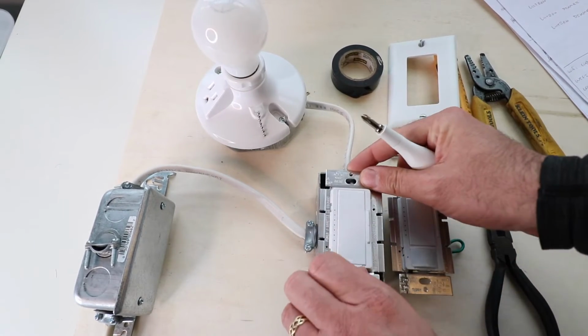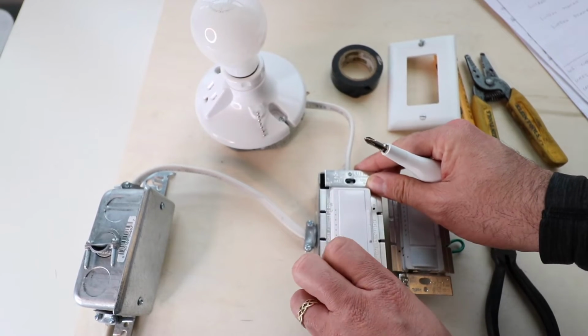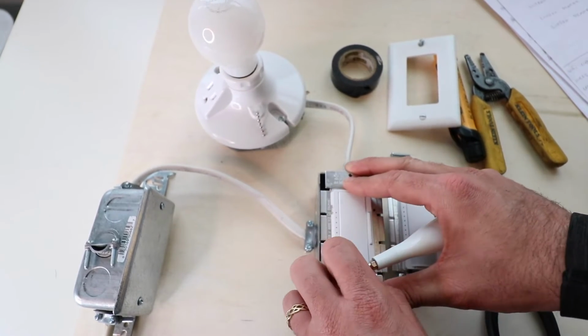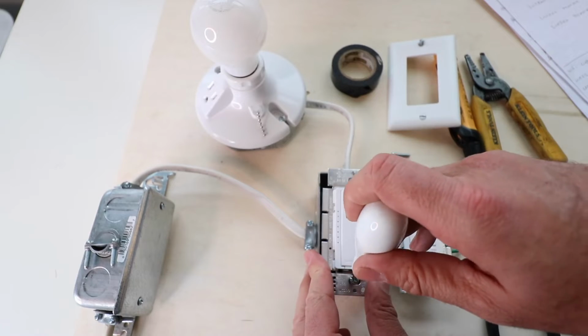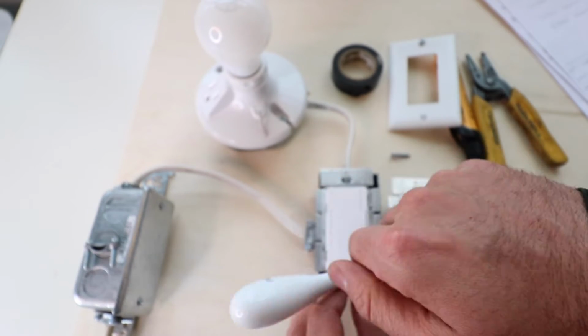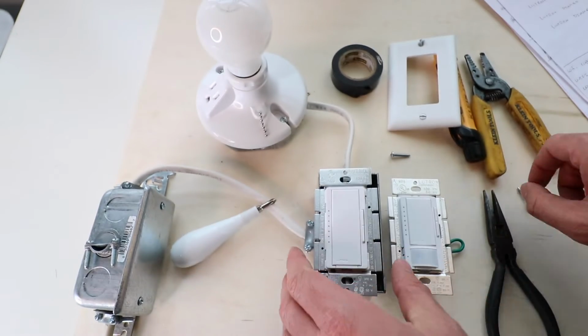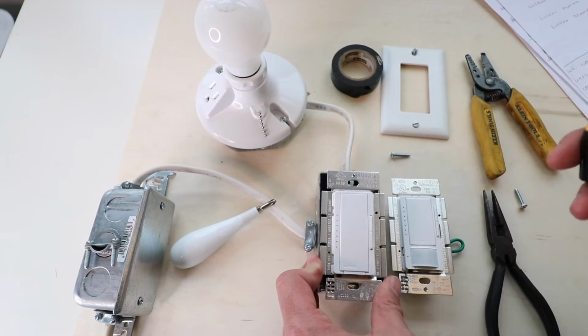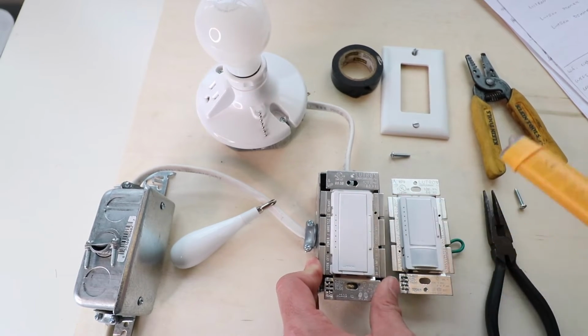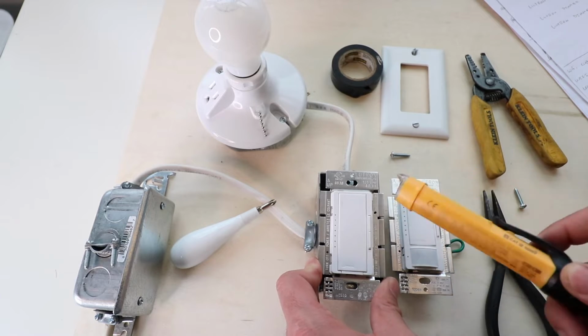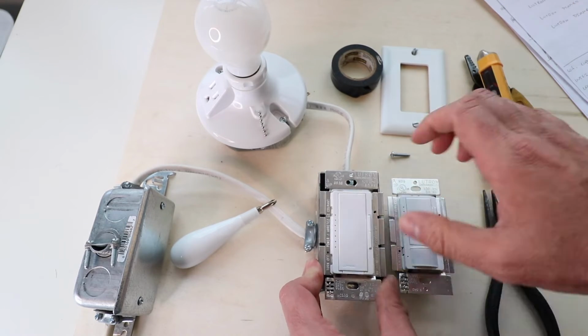All you've got to do then is remove the two screws that hold the light switch onto the junction box. We're doing that right here, just removing the two screws holding this on, and there we go. Now, if it were me, I would check this again with the non-contact voltage meter before pulling this out or loosening those screws, just something to note there.